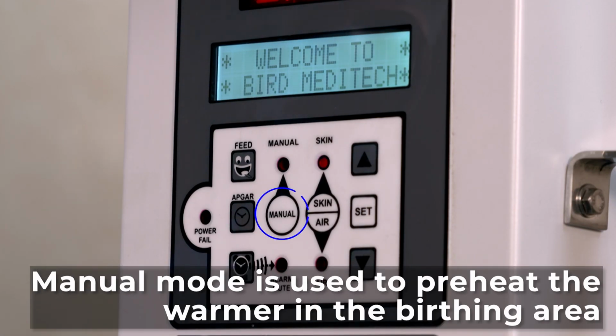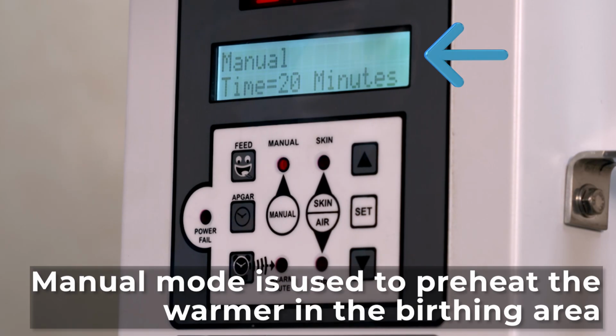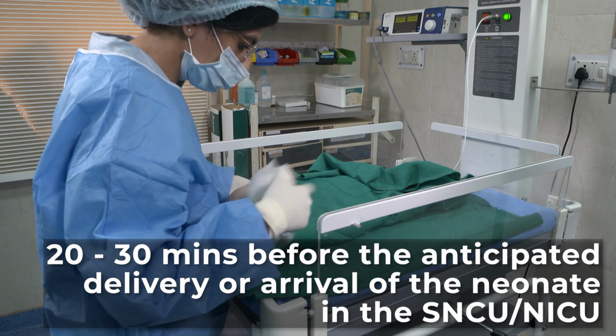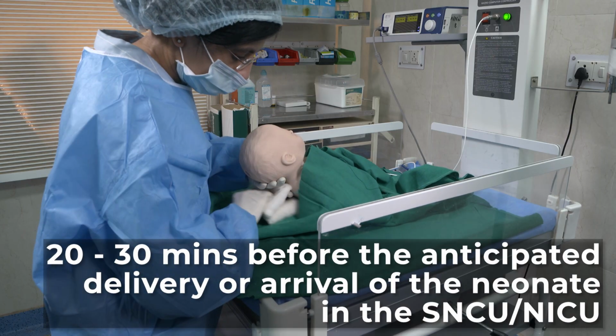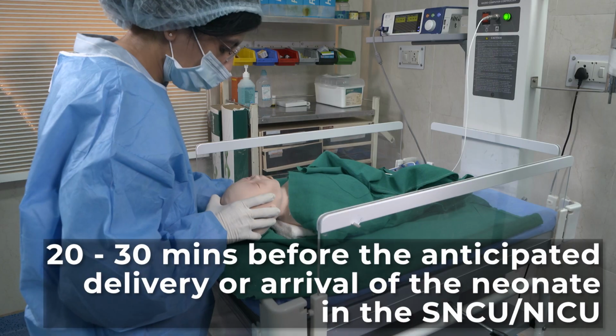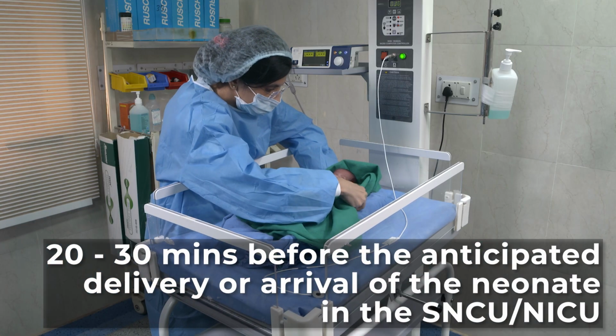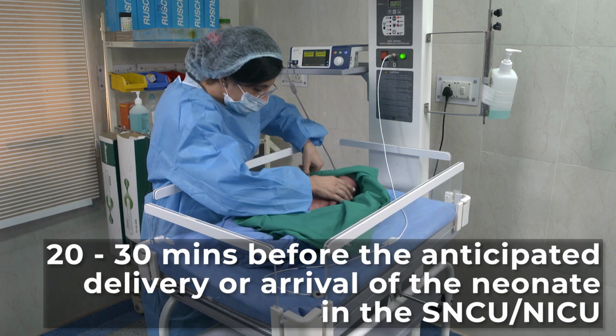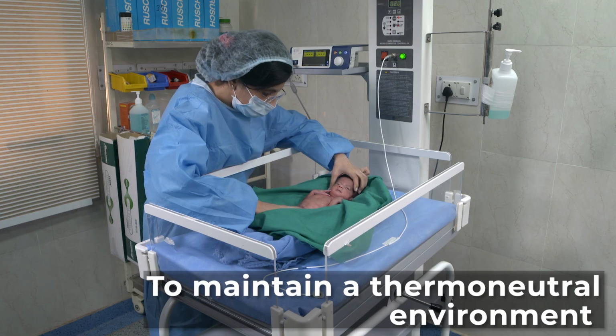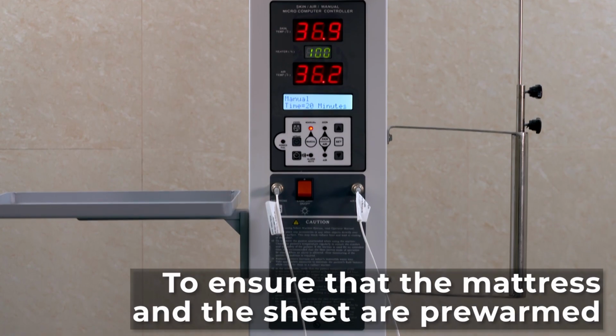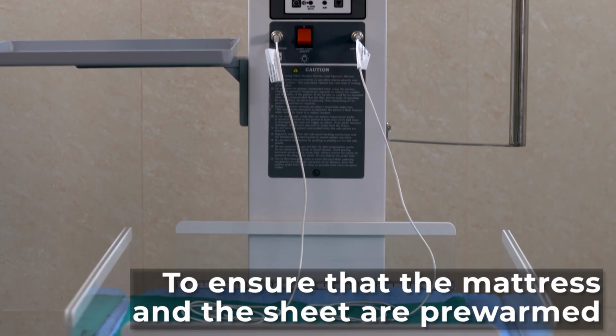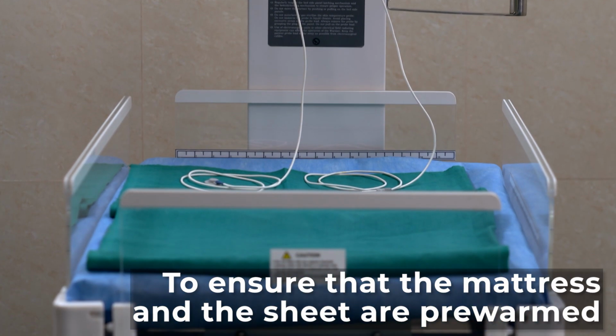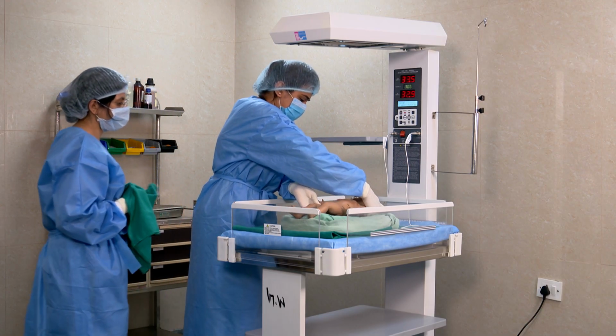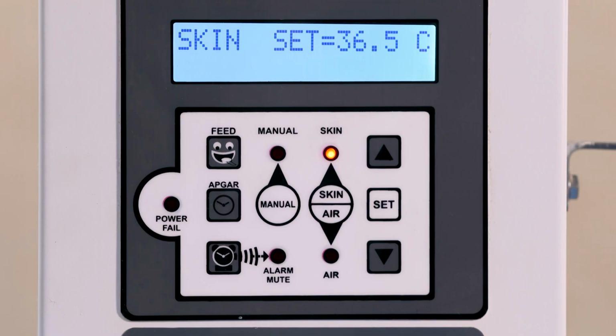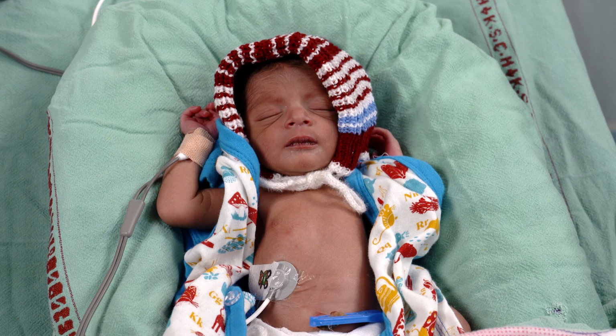Manual mode is used to preheat the warmer in the birthing area 20 to 30 minutes before the anticipated delivery and before the anticipated arrival of the neonate in the SNCU or NICU to maintain the thermoneutral environment and to ensure that the mattress and the sheet are pre-warmed before receiving the neonate. Whereas the servo mode is used in the SNCU or NICU by attaching the sensor probe to the baby's skin.